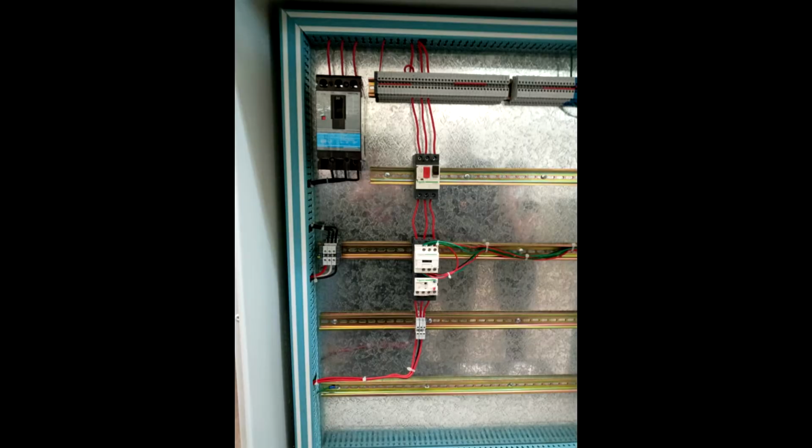Cabinet implementation. This implementation looks like how a cabinet is in the industry. It is divided into sections, control and power. The power section is composed of a disconnector as the main protection for the system. A motor starter follows the direction of the electricity. Also, it communicates the power and control sections. Then the motor is also in the power section.